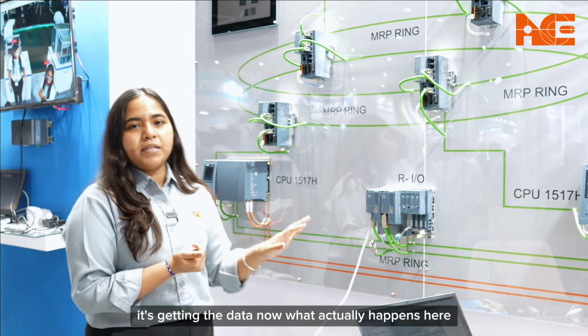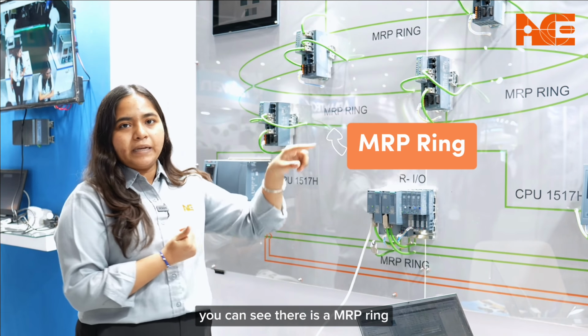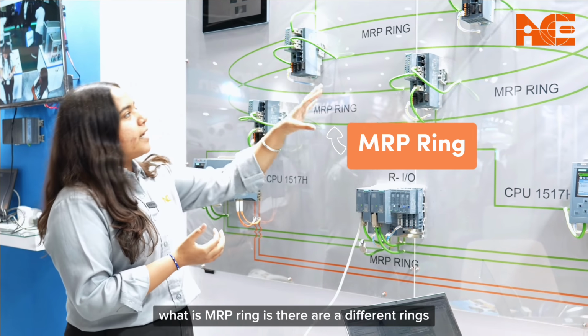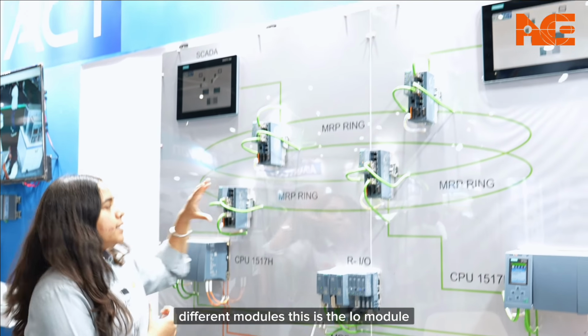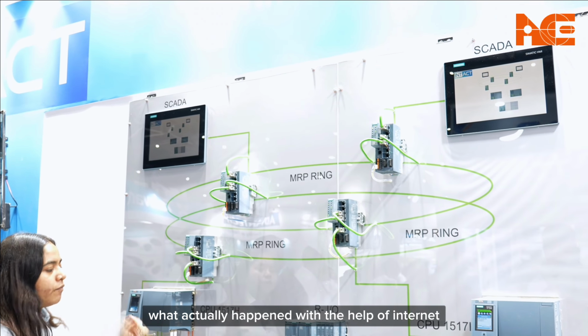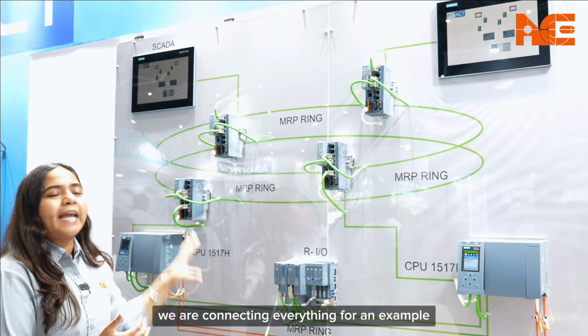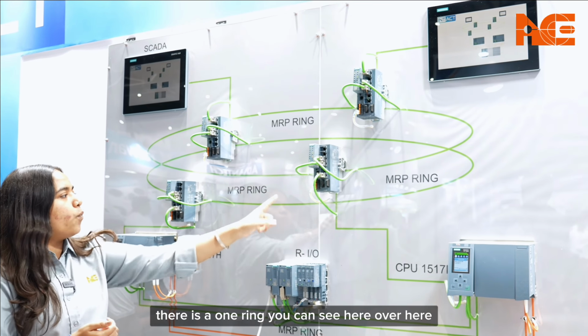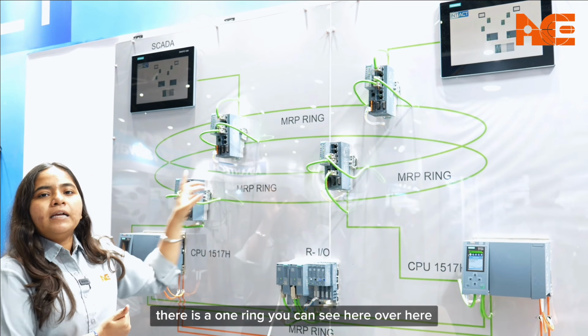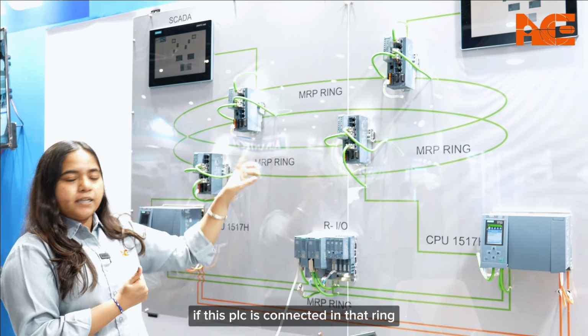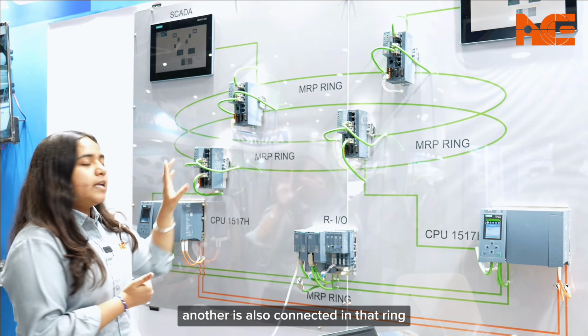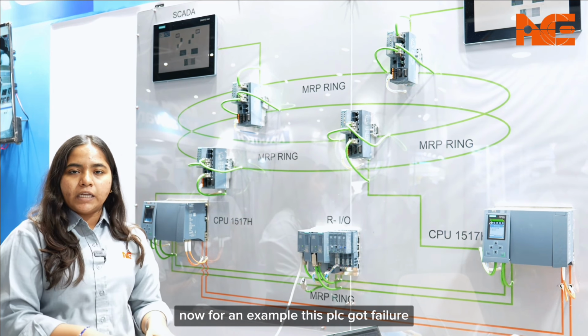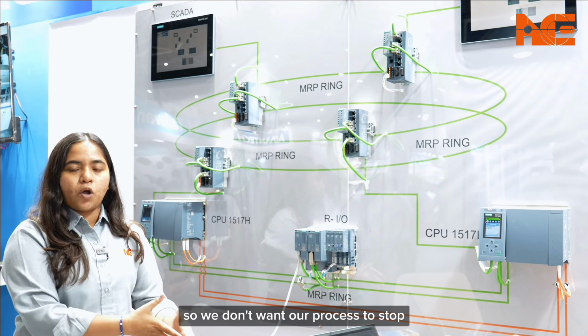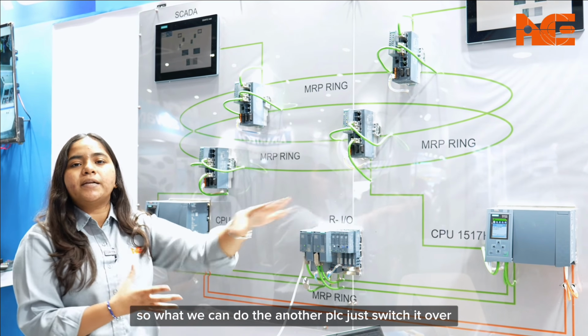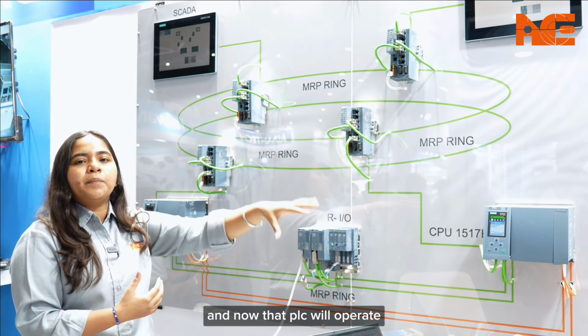Now what actually happens here, you can see there is an MRP ring. What is an MRP ring? There are different rings, different modules. This is the IO module. With the help of Ethernet we are connecting everything. For example, there is one ring you can see over here. If this PLC is connected in that ring, another is also connected in that ring. Now for example, this PLC fails, and we don't want our process to stop. So what we can do is switch over to the other PLC, and now that PLC will operate.